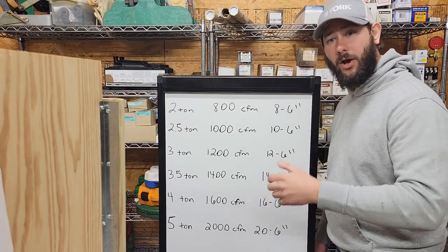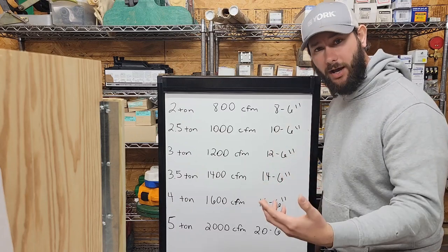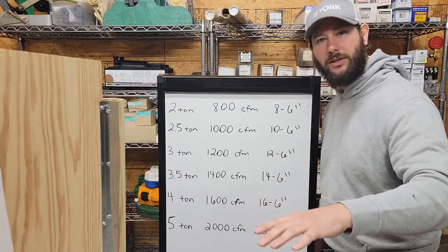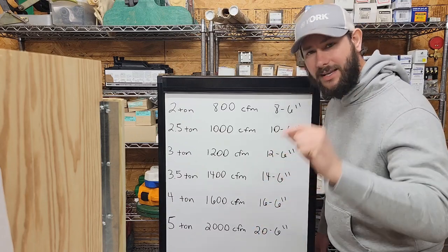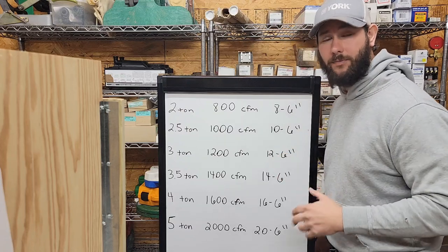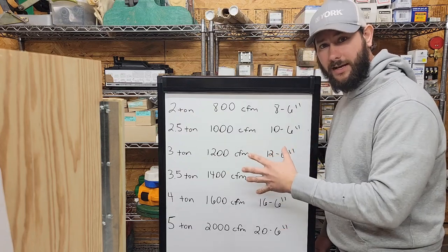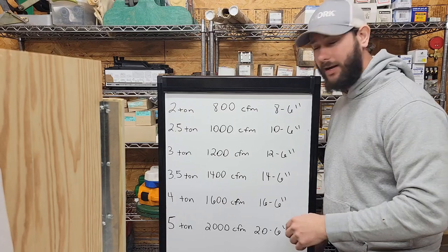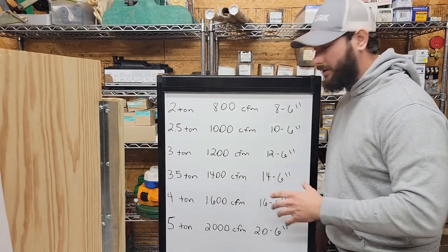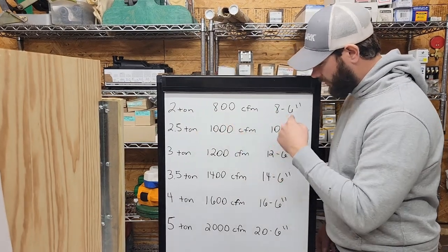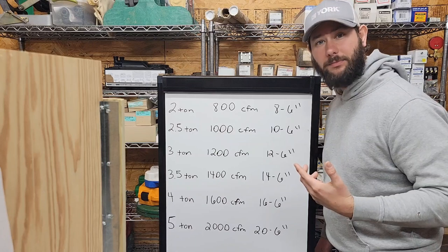What kind of system are you going to design for your duct to make sure that you have the perfect velocity coming out of every single supply register? We're also going to go over return grill sizes, which is right on the back of this board here.